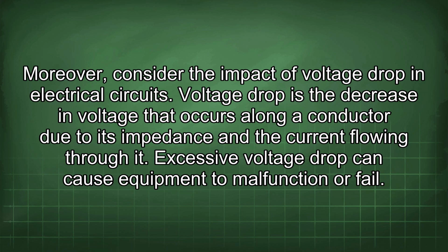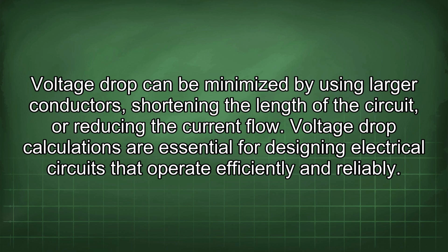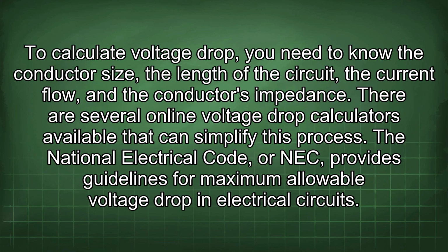Voltage drop is the decrease in voltage that occurs along a conductor due to its impedance and the current flowing through it. Excessive voltage drop can cause equipment to malfunction or fail. Voltage drop can be minimized by using larger conductors, shortening the length of the circuit, or reducing the current flow. Voltage drop calculations are essential for designing electrical circuits that operate efficiently and reliably. To calculate voltage drop, you need to know the conductor size, the length of the circuit, the current flow, and the conductor's impedance. There are several online voltage drop calculators available that can simplify this process. The National Electrical Code, or NEC, provides guidelines for maximum allowable voltage drop in electrical circuits.